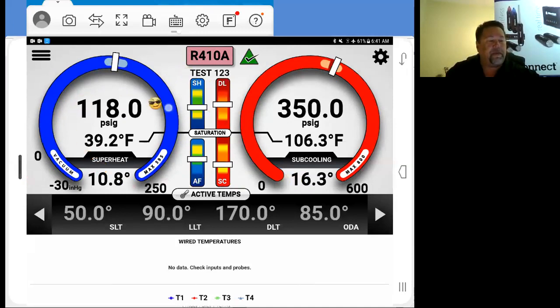Our pressures, low and high. Saturation temperatures on the evap and the condenser side. Our superheat. Now, mind you, if we were live, these numbers would be fluctuating around just a touch. But our superheat and our subcooling, our active temperatures, our suction line temp, liquid line temp, discharge line temp, and outdoor air temperature, everything's displayed. Now the profile there, that just told us what the configuration of the system was.